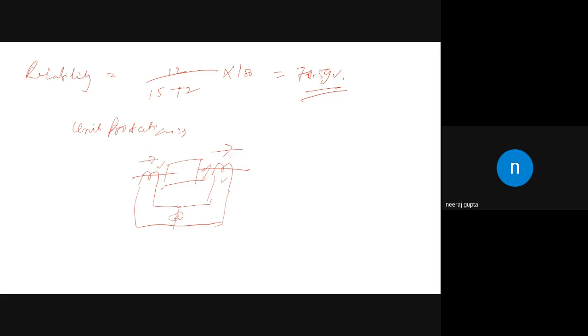So what is the unit protection? It operates for a fault within its own zone. This is the zone of the protection. The zone of the protection is decided by the CT. So unit protection means that the relay operates for a fault within its own zone, and this zone of the protection is decided by where we place the CT.